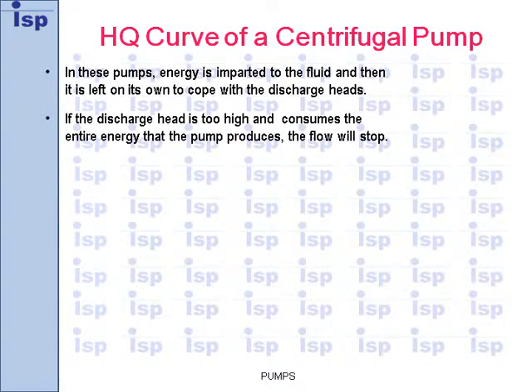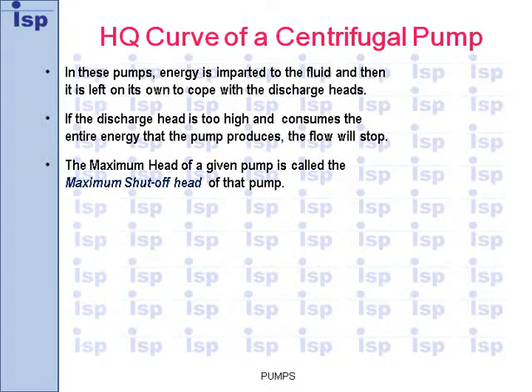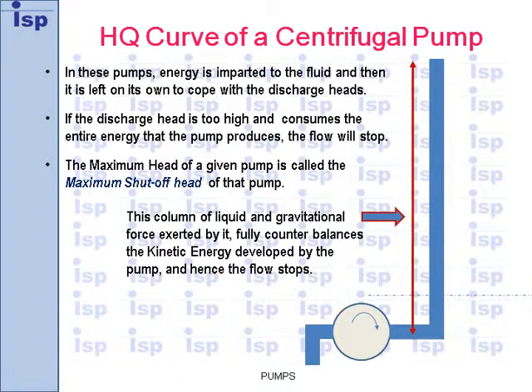HQ curve of a centrifugal pump. In these pumps, energy is imparted to the fluid and then it is left on its own to cope with the discharge heads. If the discharge head is too high and consumes the entire energy that the pump produces, the flow will stop. The maximum head of a given pump is called the maximum shut-off head of that pump. This column of liquid and the gravitational force exerted by it fully counterbalances the kinetic energy developed by the pump, and hence the flow stops.